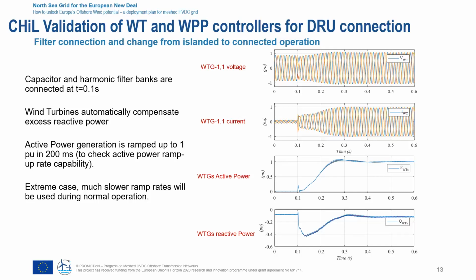So you see in these graphs the voltage on the first wind turbine, the current out of this first wind turbine, and also the active and reactive power out of each one of the wind turbines of the system. You can see that at t equals 0.1 seconds, the filters are connected, and then the power generation is ramped up and full power is reached in about 200, 300 milliseconds. This is a very large ramping rate, which is shown there just to prove that the system is operating correctly, but in an actual situation, the ramping up of the delivered power will be much slower.